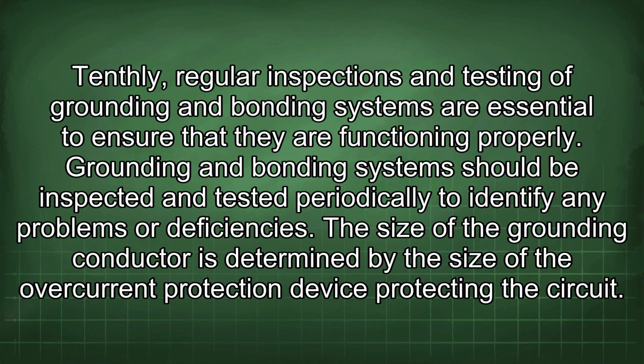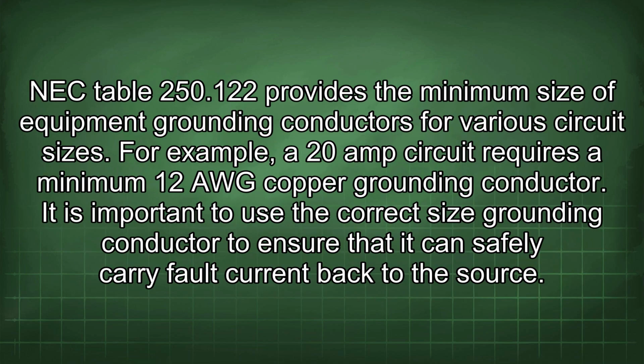The size of the grounding conductor is determined by the size of the overcurrent protection device protecting the circuit. NEC Table 250.122 provides the minimum size of equipment grounding conductors for various circuit sizes. For example, a 20 amp circuit requires a minimum 12 AWG copper grounding conductor.